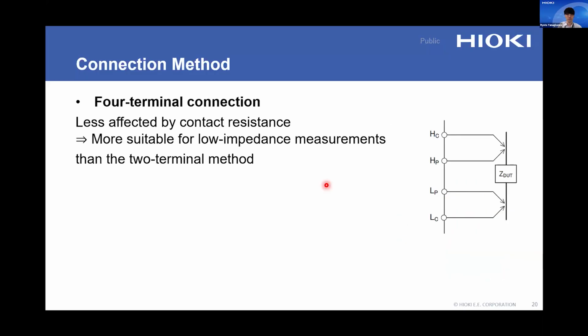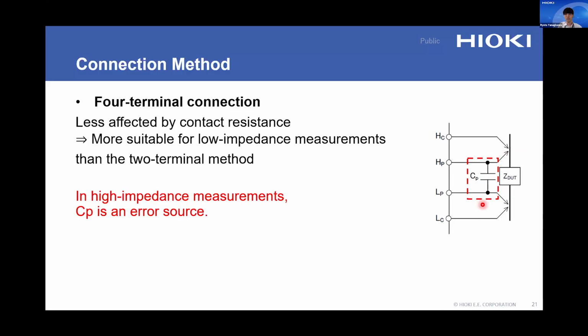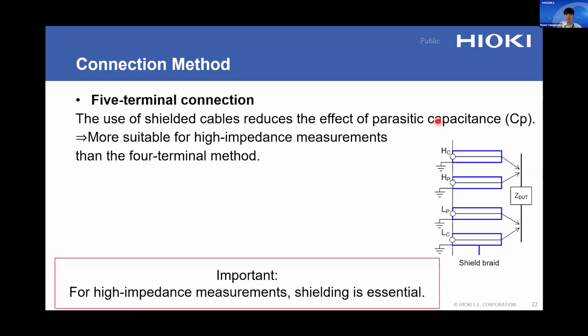Okay, next, here is the 4-terminal connection. In this method, the current and voltage terminals are connected separately to the DUT, making the measurement less affected by contact resistance. Since contact resistance is typically on the order of milliohms, the 4-terminal method is recommended compared to the 2-terminal method for low impedance measurement, where this effect becomes significant. However, in high impedance measurement, it is affected by parasitic capacitance like this, just like the 2-terminal connection. To achieve accurate high impedance measurement, proper shielding is essential.